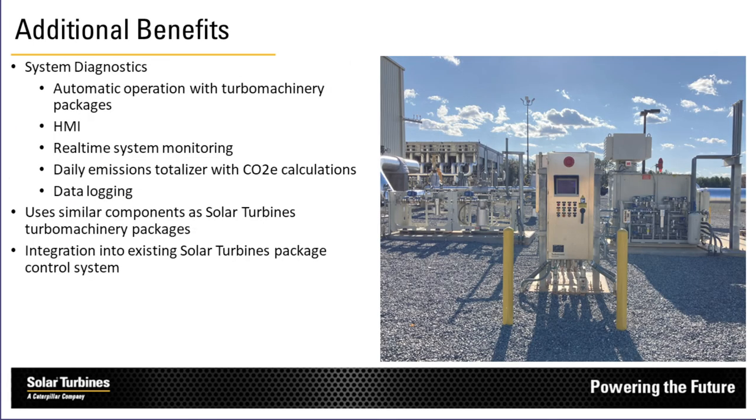There are several additional benefits I would like to talk about with the system here. One of the key items is that it has a lot of system diagnostics associated with it. It was designed with the intent to suit any site around the world, and especially to support remote sites. So it has automatic operation with the turbomachinery packages on site, with very few discrete signals between the two, and so operator intervention is not required. It does have its own HMI and real-time monitoring for customers who want to connect and gather their own information about performance, how much CO2 equivalency they are capturing, and what the run rates are. That's all available to them through this system. And on the HMI, we do daily totalizers with the CO2 equivalencies in them.